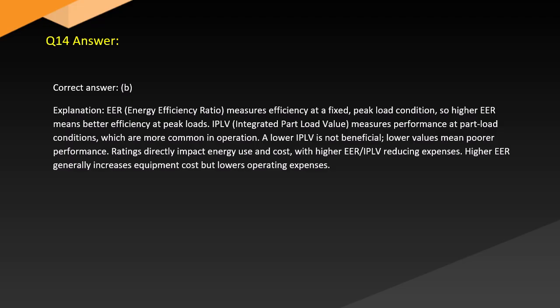Answer. Correct answer, B. Explanation. The energy efficiency ratio measures efficiency at a fixed peak load condition, so higher EER means better efficiency at peak loads. IPLV, integrated part load value, measures performance at part load conditions, which are more common in operation. A lower IPLV is not beneficial. Lower values mean poorer performance. Ratings directly impact energy use and cost, with higher EER reducing expenses. Higher EER generally increases equipment cost but lowers operating expenses.